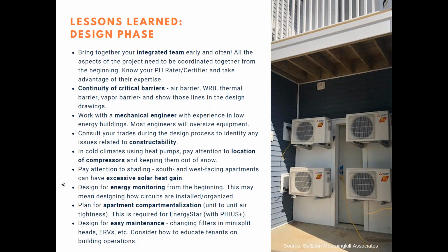This is not a requirement for passive house certification. However, if after the building has been operated for a while the energy use is not matching your model, you're going to want to investigate and figure out what's going on. So organizing your circuits so that you can separate out hot water, mini splits, on one circuit, lets you go back and do some analysis and track down the sources of energy use. That's really helpful.